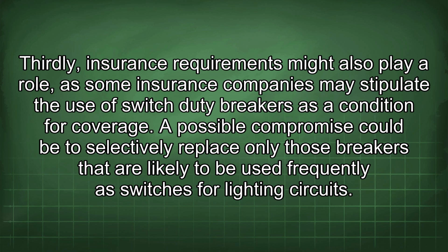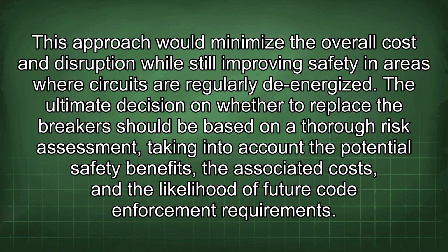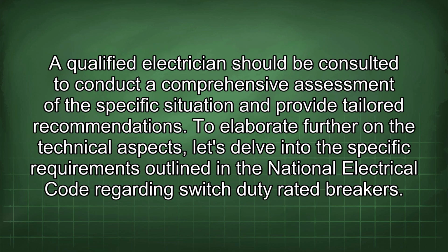A possible compromise could be to selectively replace only those breakers that are likely to be used frequently as switches for lighting circuits. This approach would minimize the overall cost and disruption while still improving safety in areas where circuits are regularly de-energized. The ultimate decision on whether to replace the breakers should be based on a thorough risk assessment, taking into account the potential safety benefits, the associated costs, and the likelihood of future code enforcement requirements. A qualified electrician should be consulted to conduct a comprehensive assessment of the specific situation and provide tailored recommendations.